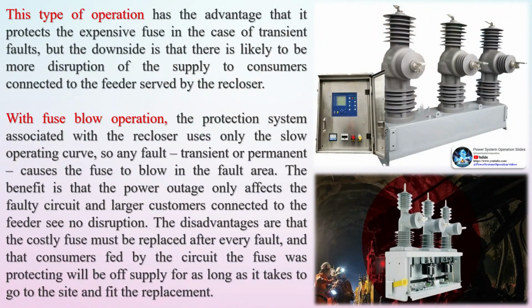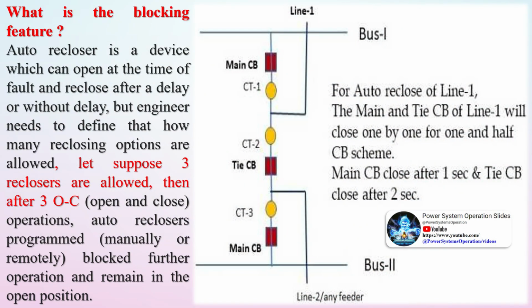During lightning on the transmission system, the phase-to-earth fault occurs and which is in transient nature. Whenever any phase-to-earth fault occurred in the transmission line, the distance relay detects the fault and it will trip that phase of the circuit breaker of the line to isolate the fault. Except for that phase, other healthy phases will remain close position. The open CB pole of the faulty phase is again close after 1 second by an auto-recloser relay. If the fault is in transient nature, in that case, the fault may clear within 1 second and after the closing of the CB pole, the line will hold or power will remain flowing.